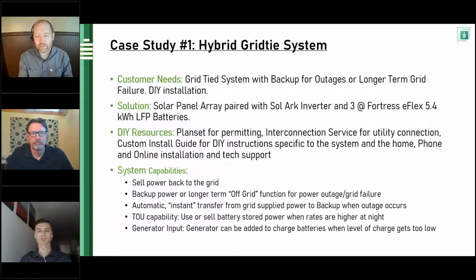I've lived off grid since about 2008, and for the longest time I only lived on 8 batteries, 8 L16 batteries. Our battery monitor, we'd use about 60 to 80 amp hours a night, which is 3 to 4 kilowatt hours per cycle. So 15 kilowatt hours of lithium, I would have almost 3 days of backup there, 2 days for sure. So it's a decent sized battery bank.